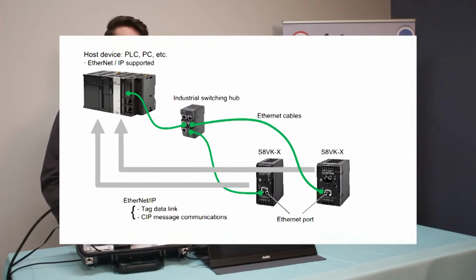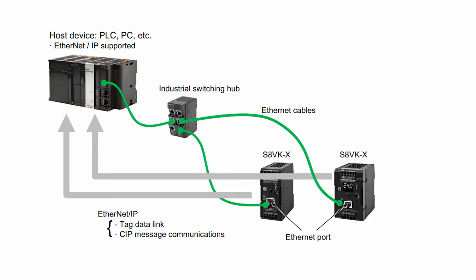The smartest thing about this power supply is the integrated Ethernet IP communications, which allow you to monitor those metrics remotely when connected to a PC, PLC, or machine automation controller. But this is where it gets pretty interesting. You can set the maximum output current, and if that threshold is surpassed, an alarm will trigger.